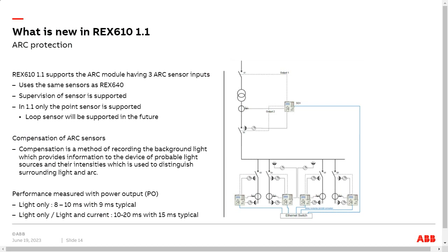That also means that these sensors are supervised. So in case, for example, the cable comes loose or is physically broken, you will get an alarm, or a message, that the sensor is not operational anymore. Then, as a small note, this 1.1 firmware only supports the point sensor, and of course the loop sensor will be supported in the future. This will come sometime in the future, and it will also be a firmware update only. So you will also get loop support on REX610 with the same module.